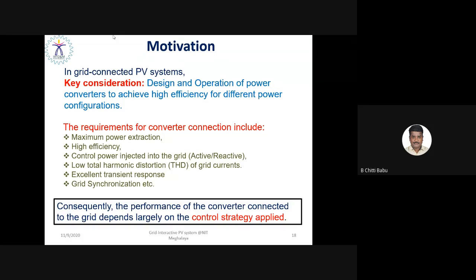So the power electronics converter is a candidate that provides an asynchronous interface between the solar PV system and the utility grid. The key consideration of integrating a solar PV system is basically the design and operation of the power converter to achieve high efficiency for different power configurations. The requirements for the power converter connection include maximum power extraction and high efficiency, controllable active as well as reactive power injected into the utility grid, and lower total harmonic distortion of the grid current. It should have an excellent transient response during grid abnormalities, and it also includes grid synchronization. I mean, the inverter output frequency must be well synchronized with the grid frequency so that we are able to integrate a solar PV system with the utility grid through the power converter.